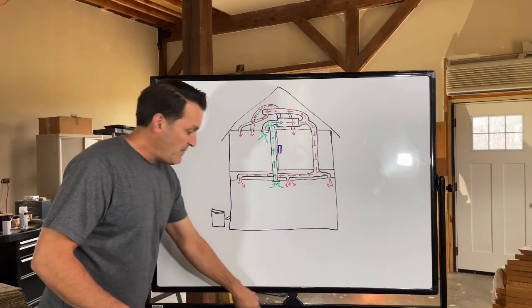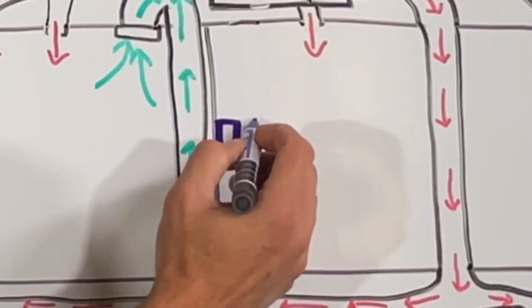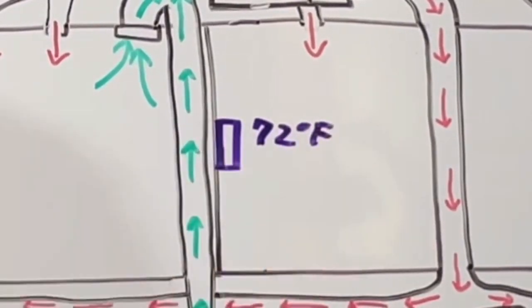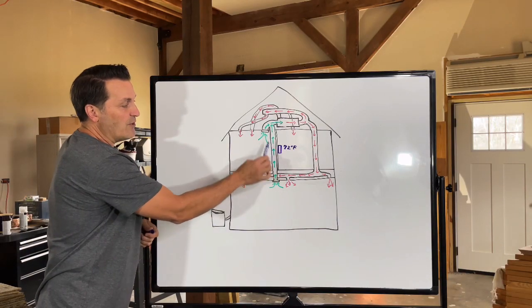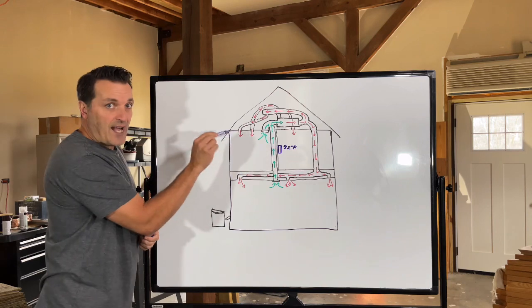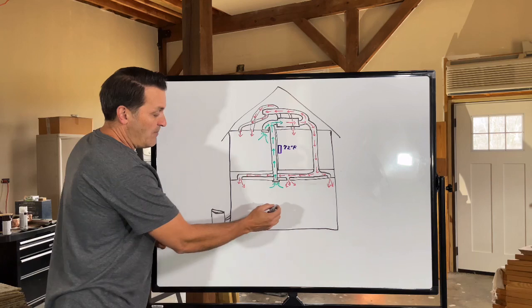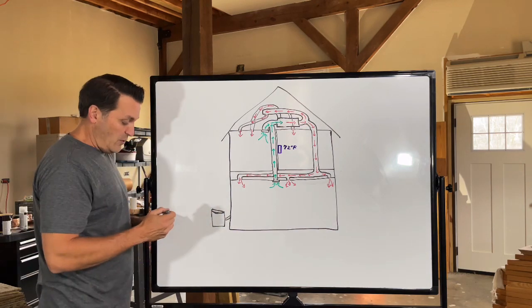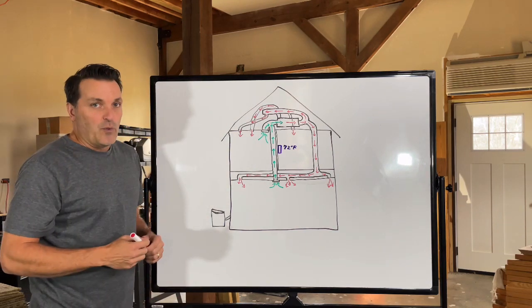So if you set that thermostat, let's say you set the thermostat to 72 degrees upstairs, that thermostat is going to kick on and it's going to run until the temperature at the thermostat reaches 72 degrees. Now down here, we know that the main floor is usually always going to be cooler due to what's called the stack effect or thermal effect.